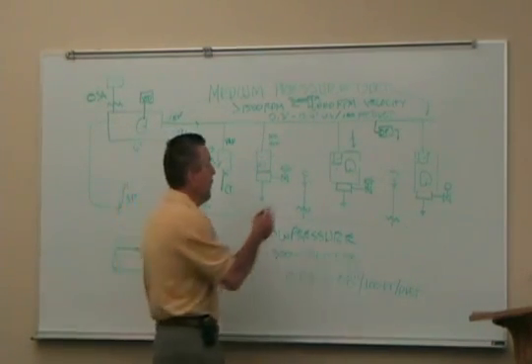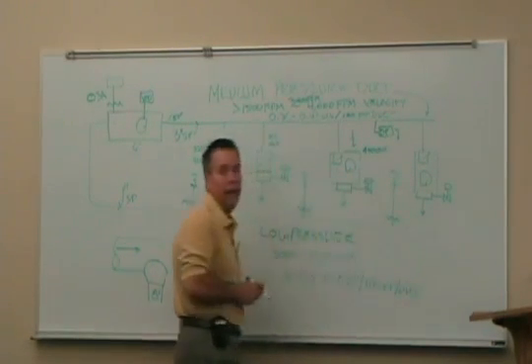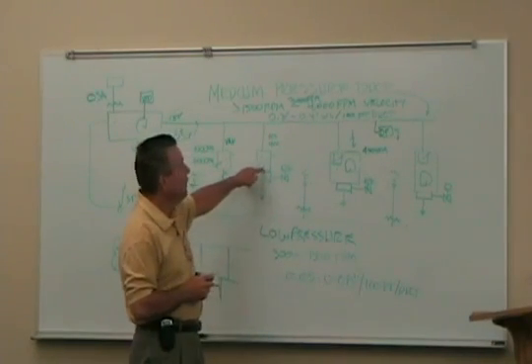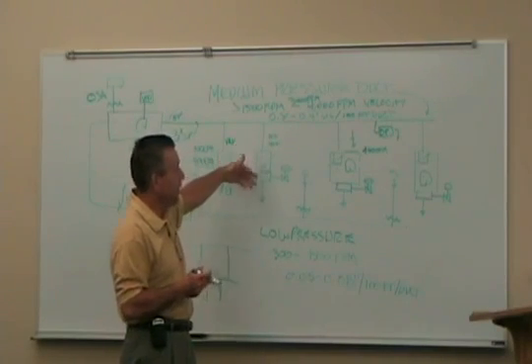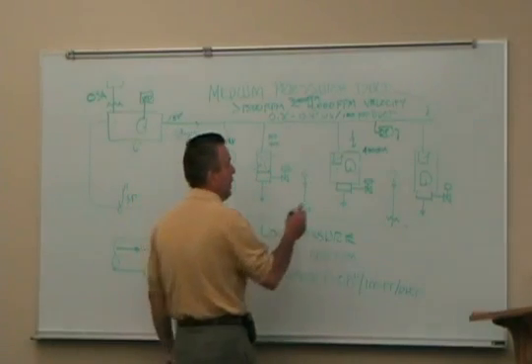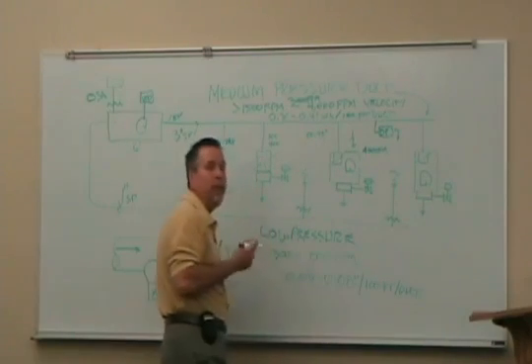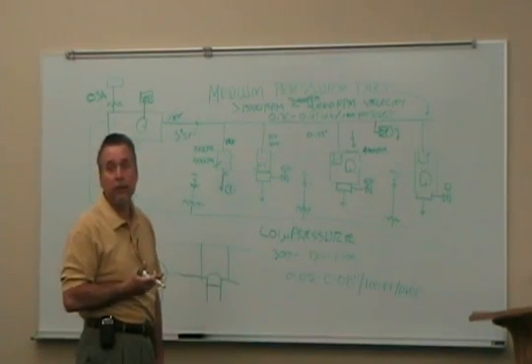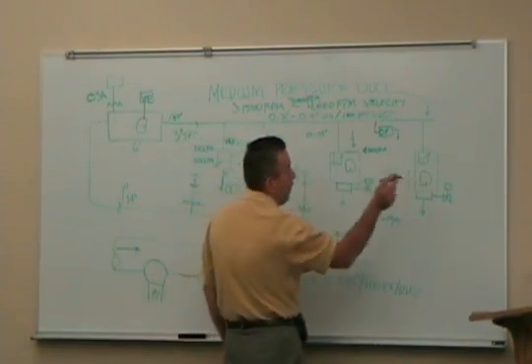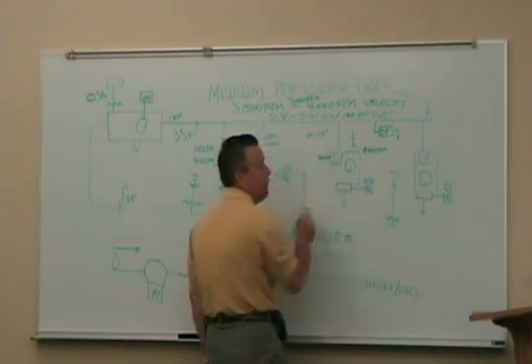Okay? So this box is 400 CFM all the time. So what happens is, in this case, my damper's wide open or modulated to some position that gives me 400 CFM. I've got to reheat that 400 CFM all the time. So from 55, probably up to room neutral conditions of 75. I'm reheating that air all the time. It's an energy waster, right? So I use a fan-powered box and the controller tells this box to close to 100 CFM to meet my ventilation.